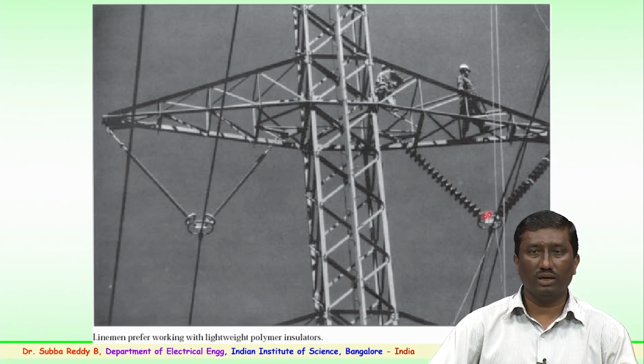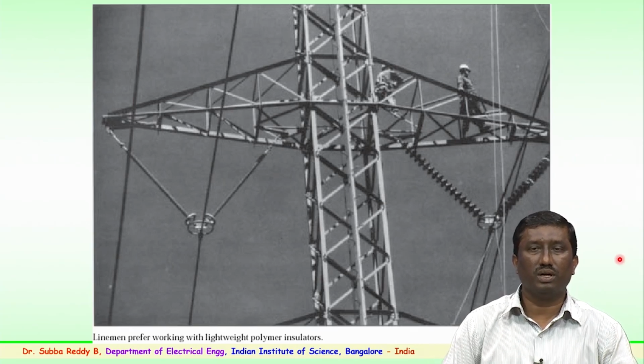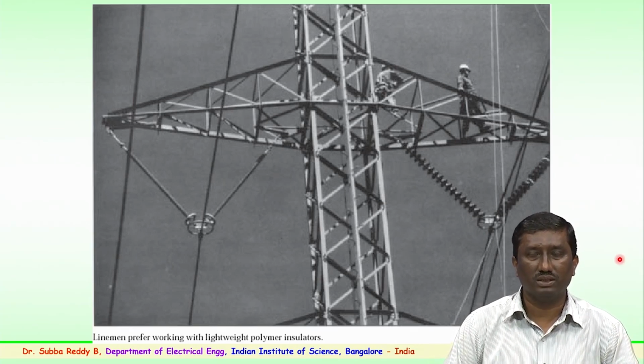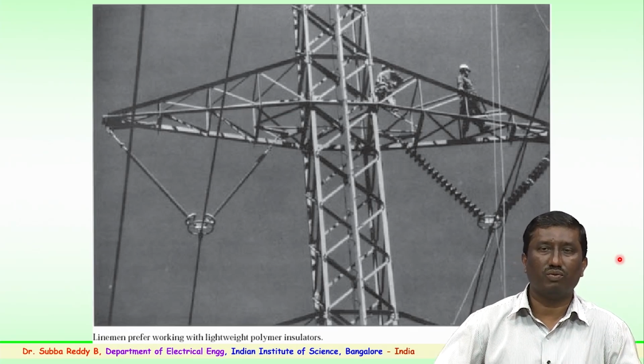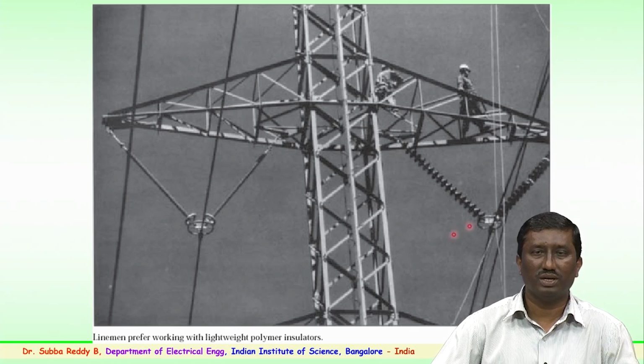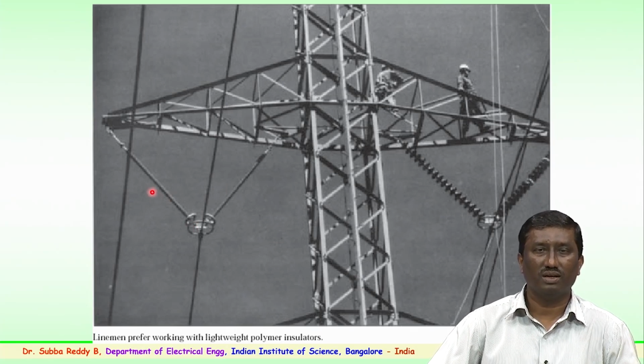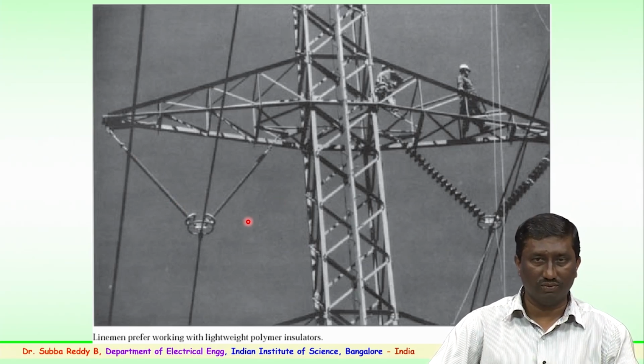So, 23 into 2 is 46 insulators, and each insulator weighs somewhere around 10 to 12 kg. So, around 500 kilos plus the hardware, it comes to around 1 ton in the case of a ceramic insulator, whereas for a polymer insulator, each will weigh a few 10 to 12 kg. So, totally the weight reduction will be more than 60 to 70% here.